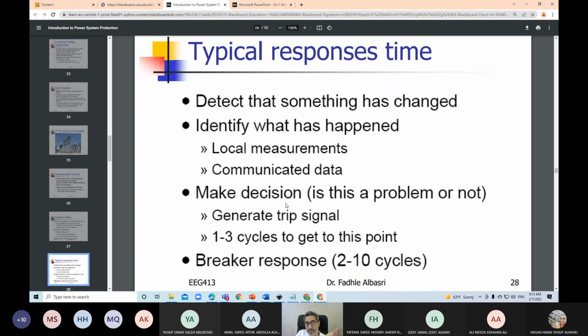Then it decides whether this is abnormal or a short circuit, for example, and if it is in the area that this relay is responsible for, it will take a trip action within 1 to 3 cycles. Nowadays relays in transmission systems are very fast. One cycle means 20 milliseconds. We have very fast relays working in 3 milliseconds, and their working principle is based on traveling waves. After they detect a fault within, let's say, 1 cycle, they give a command to a circuit breaker to trip.